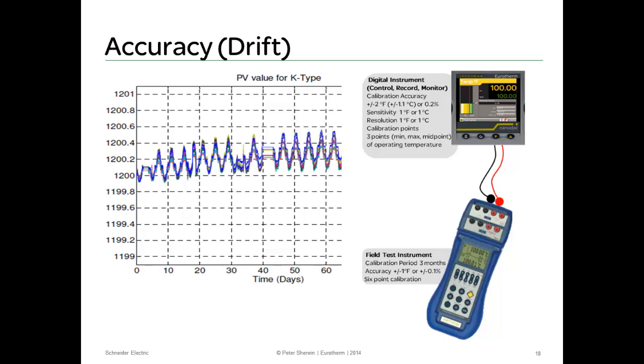Calibration applies equally to process instrumentation and field instruments. In process instruments, AMS specifies intervals between 1 month for class 1 furnaces to 6 months for class 5 and 6 furnaces. Apart from the theoretical calculations of drift, we also put our devices through laboratory tests, cycling ambient conditions over a period of time to evaluate the drift characteristics. Ambient temperatures cycling within 25 degrees Fahrenheit can lead to drift results at 60-70% of theoretical levels. Keeping a control cabinet at a constant temperature then really helps with calibration results over time.